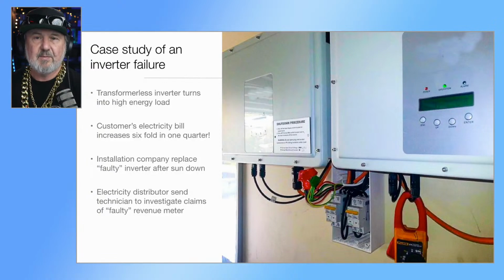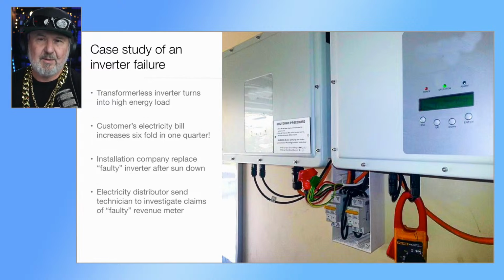Yeah, so this was a system installed back in 2007 and 2010. And in 2010, it wasn't actually a requirement to have a bonding of the PV array to earth. So you got to actually just put your PV array on the roof, put your panels up and run your cables. You didn't have to have an earth bonded rail or module. And this problem probably would have still happened, but maybe the inverter might have survived and been able to shut down in time. But the reality is that inverters don't respond well to having what's called a bolted fault on their terminals, on their DC input.